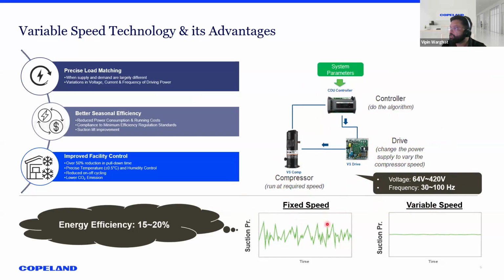So in actual operation, a fixed speed compressor will be operating at various suction pressures because of its nature of operating at a fixed speed, which ultimately is going to cause a lot of increase in on-off cycles. It will also not maintain the precise temperature, and ultimately it is not going to maintain the right humidity in the cold room.